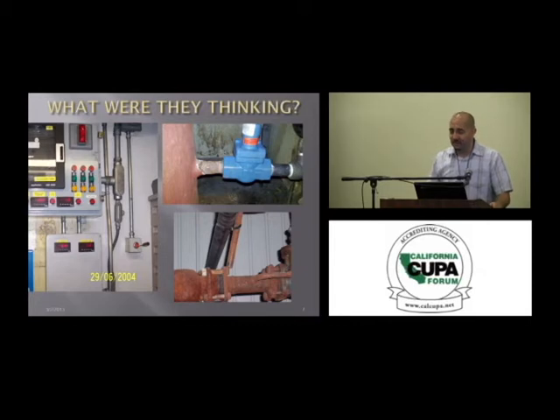The recommendation on that was what? Whack it off. Whack it off and replace the nipple. When I make the recommendation, I ensure that the pipe is safe for further use. Visually looking at that, I know that it's not. So pump down, cut, replace, weld a new nipple on there, and be safe.